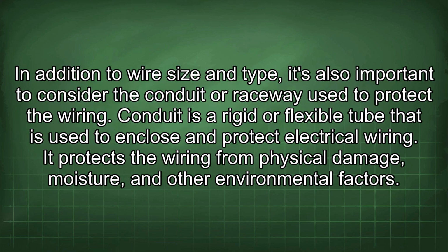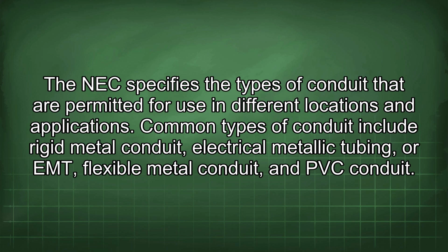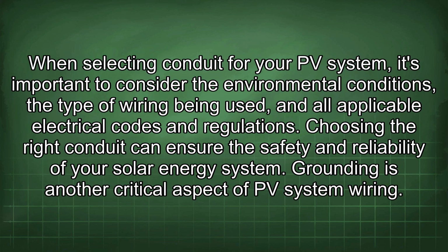In addition to wire size and type, it's also important to consider the conduit or raceway used to protect the wiring. Conduit is a rigid or flexible tube that is used to enclose and protect electrical wiring. It protects the wiring from physical damage, moisture, and other environmental factors. The NEC specifies the types of conduit that are permitted for use in different locations and applications. Common types of conduit include rigid metal conduit, electrical metallic tubing, or EMT, flexible metal conduit, and PVC conduit. When selecting conduit for your PV system, it's important to consider the environmental conditions, the type of wiring being used, and all applicable electrical codes and regulations. Choosing the right conduit can ensure the safety and reliability of your solar energy system.